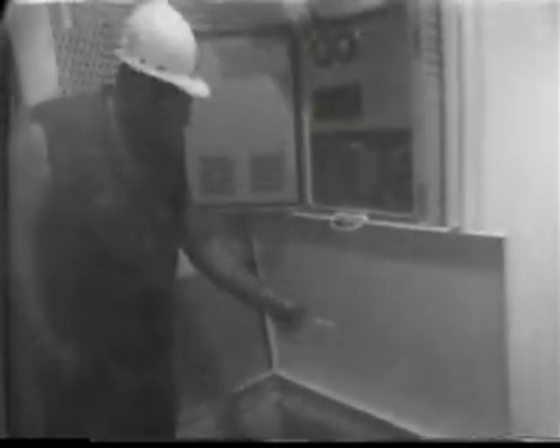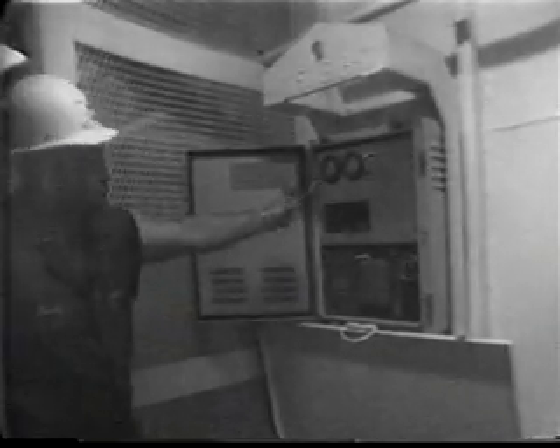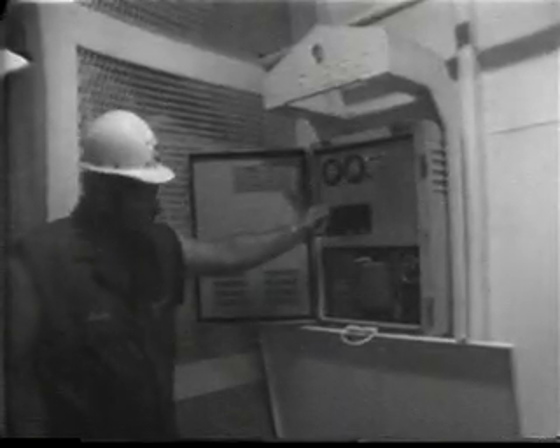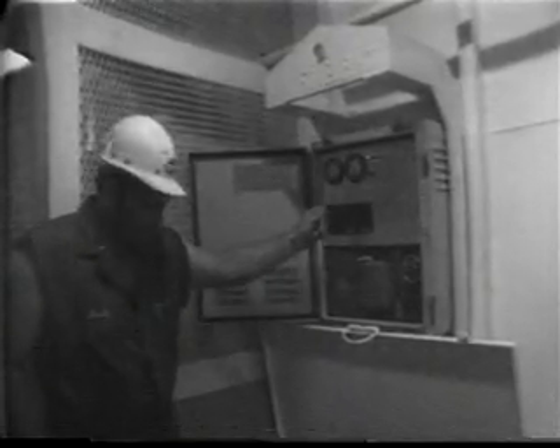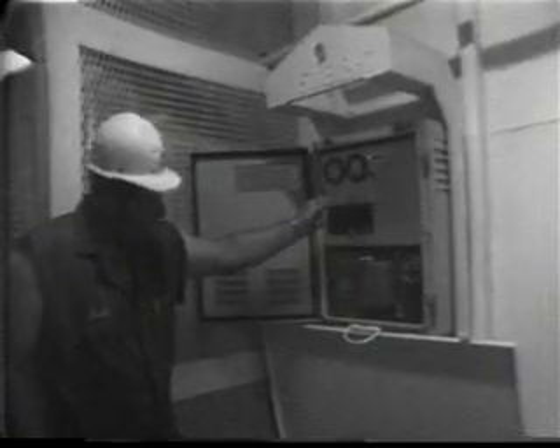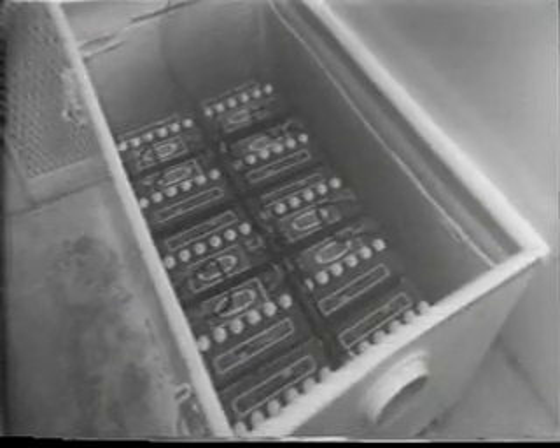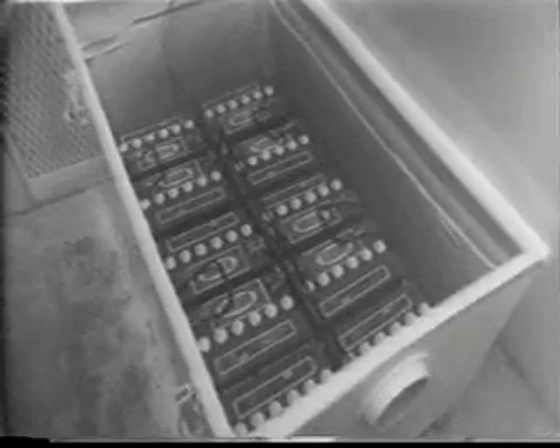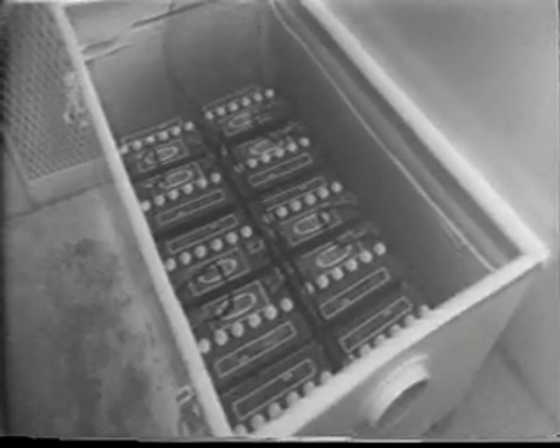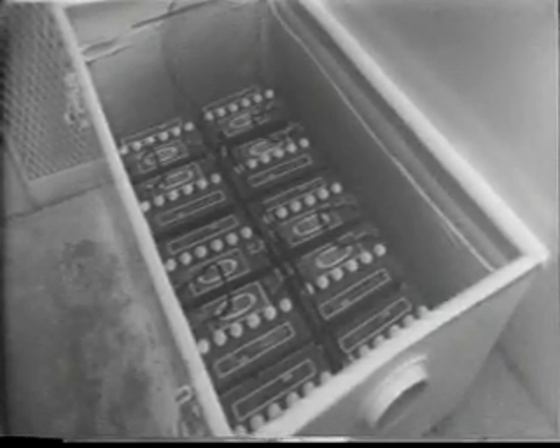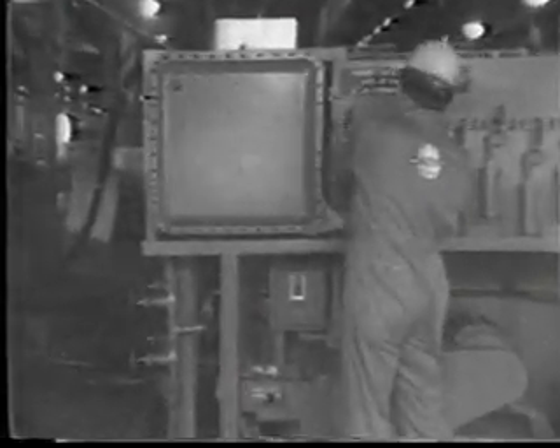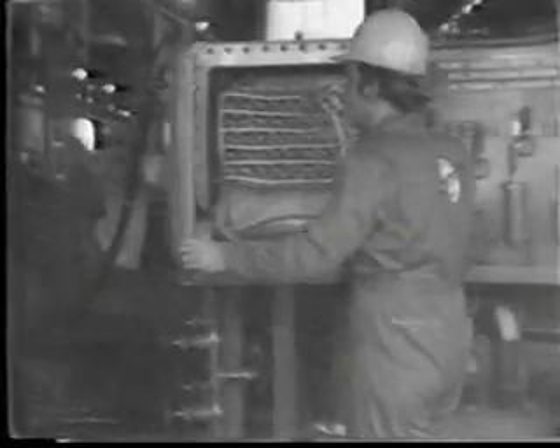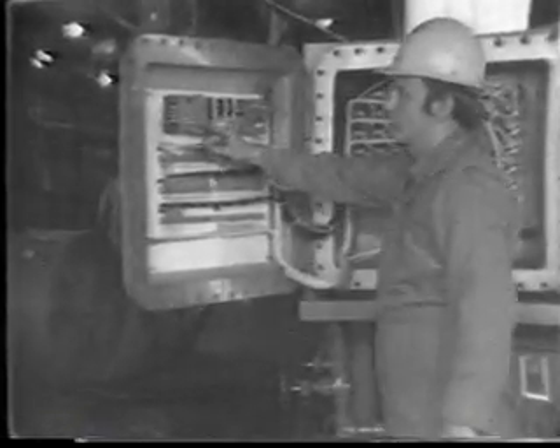The second function performed by the power pack is that of standby power. In the event of a rig power failure, the batteries contained in the power pack automatically take over and provide the correct system voltage, either 120 volts DC or 24 volts DC, that is required to operate the system. These batteries can power the system for approximately 18 hours. However, this time will vary depending on the load requirement of the system.